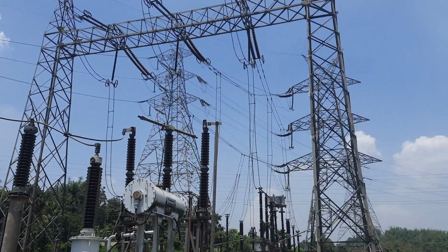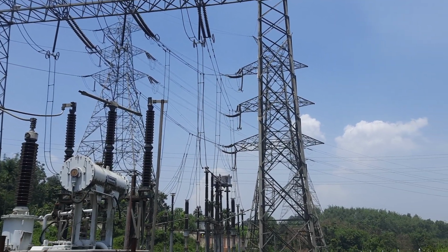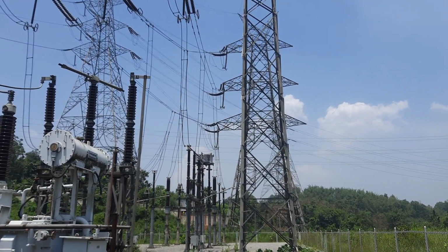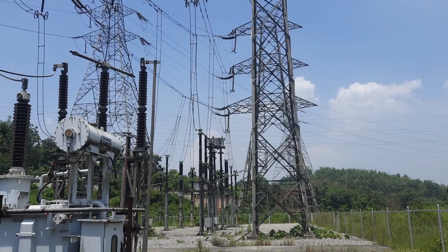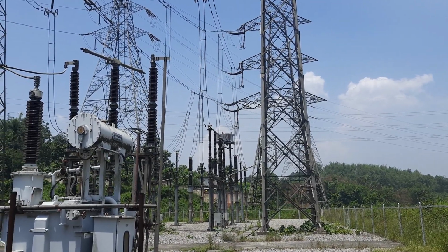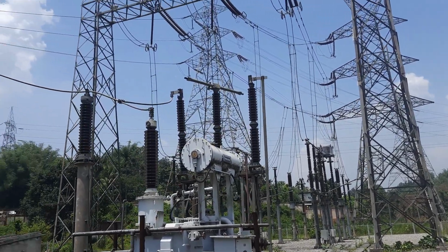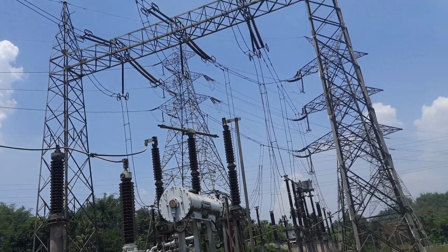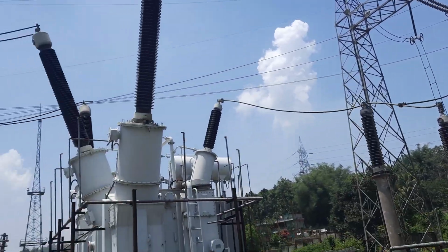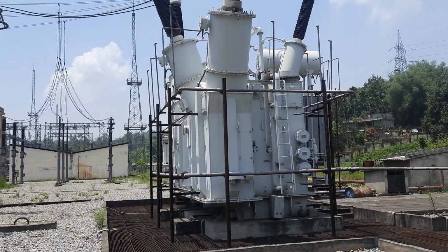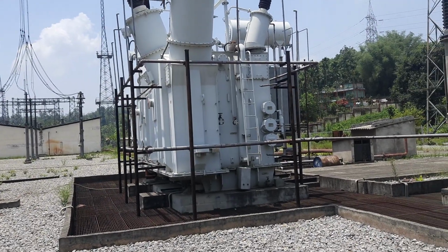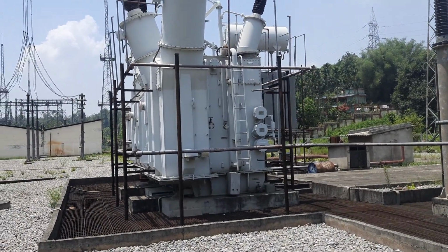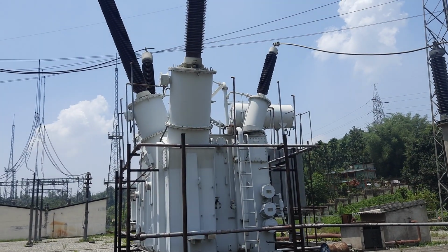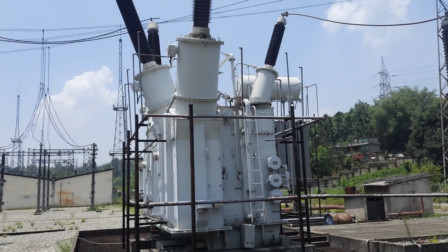a long transmission line, there is a possibility of the receiving end having more voltage than the sending end, and because of that, to compensate for it or to bring down the voltage level, we have to absorb the reactive power, and for absorbing the reactive power we are keeping this reactor. So the capacity has been calculated accordingly, and 50 MVAR is the capacity of this shunt reactor.